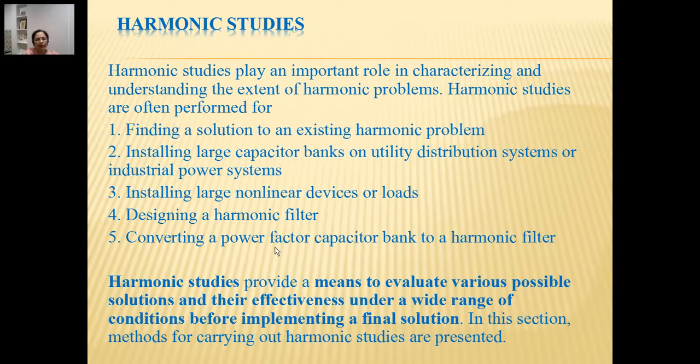When we are installing a power factor correction capacitor, if it can also be used as a harmonic filter, first we need to understand which order harmonic we are interested in filtering out. Accordingly, the capacitor value should be chosen by checking how much power factor correction it can provide as well as work as a harmonic filter. So harmonic studies come in very handy in all these cases.